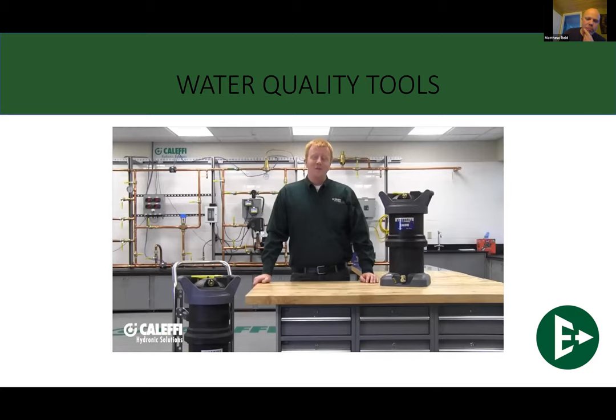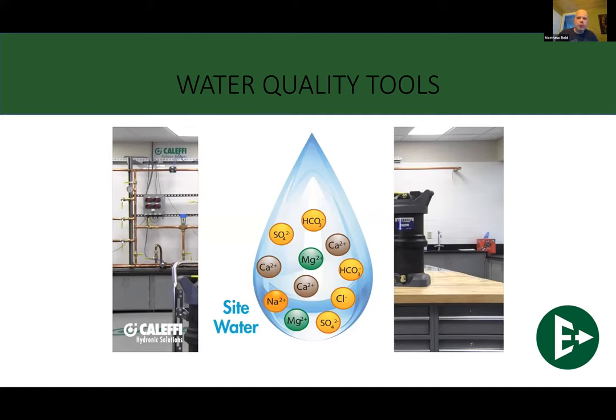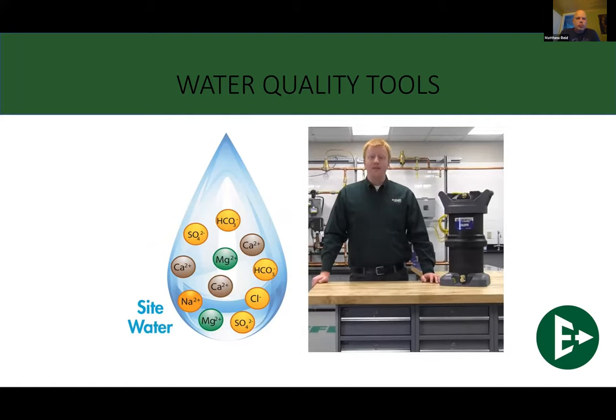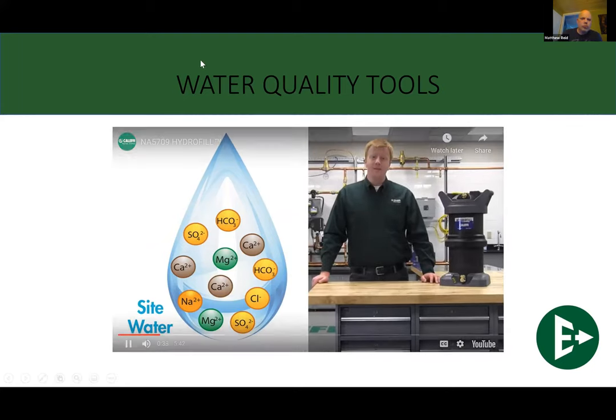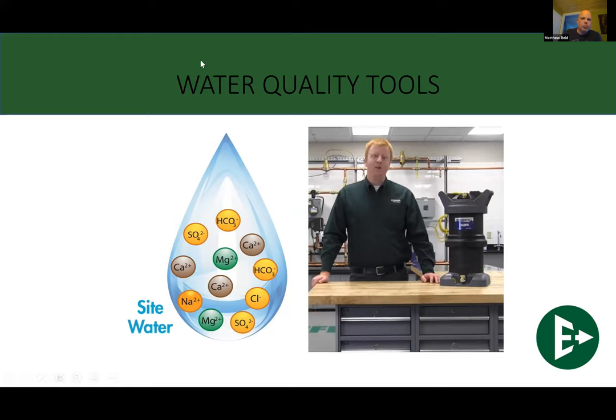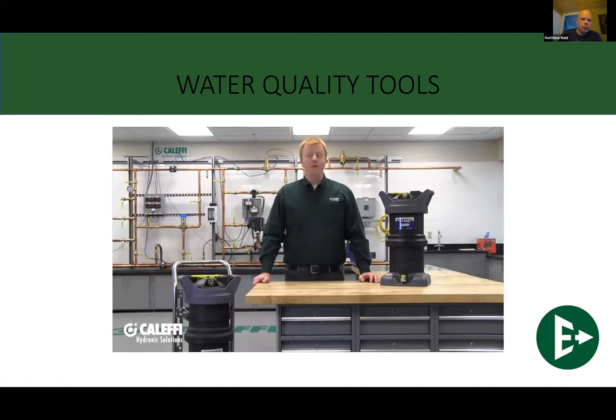The Hydrofill is used to fill closed-loop hydronic systems with demineralized water using tap water available on site. What you may not realize is that in most cases, the tap water available on site does not meet the strict requirements for water quality set forth by the equipment manufacturers, thus the need for the Hydrofill. So let's go over the features on the two Hydrofill models that we have available.